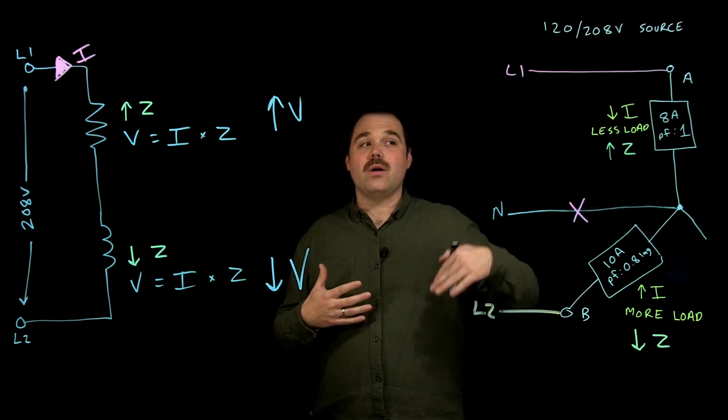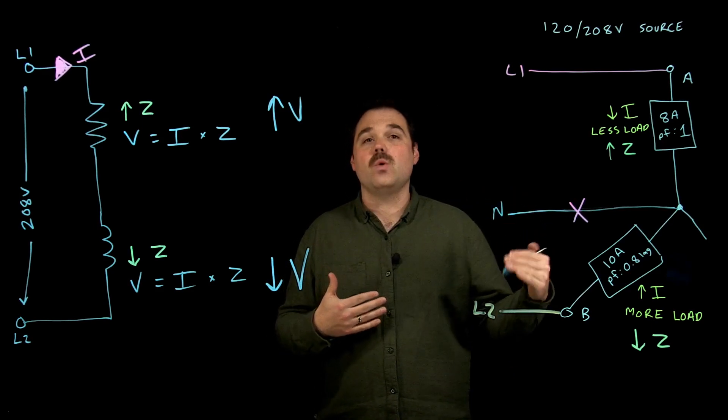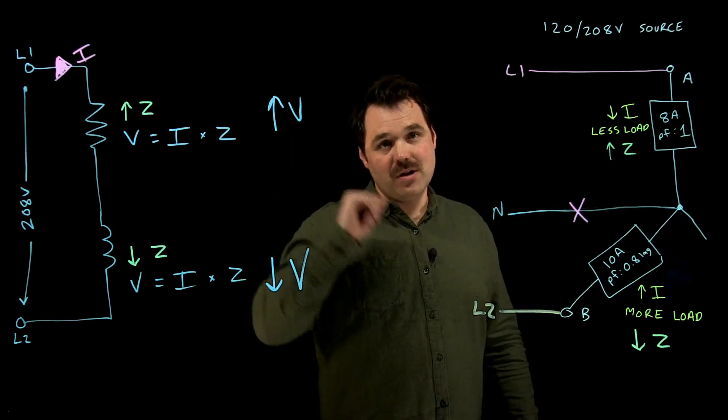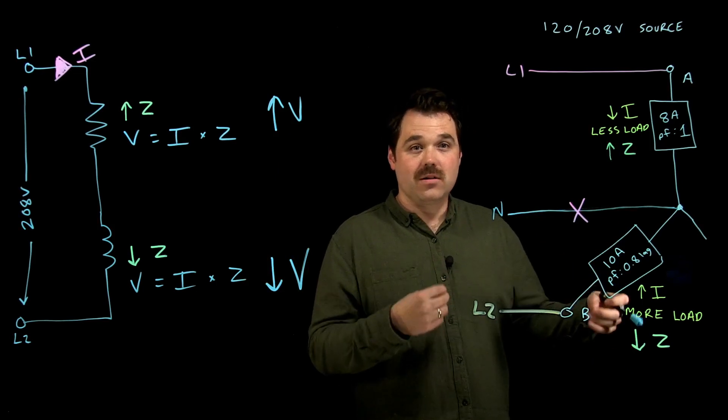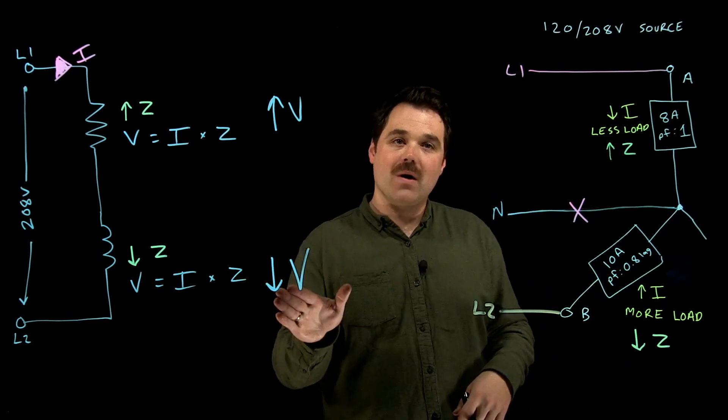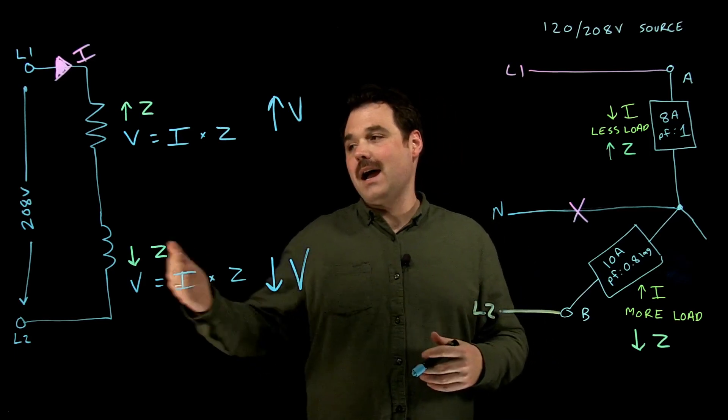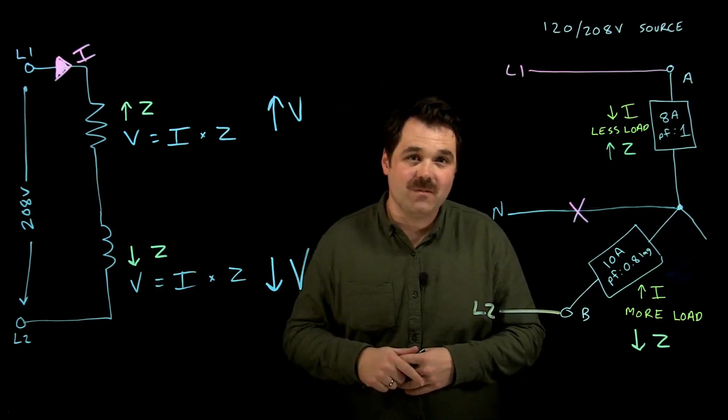So again, our least loaded circuit or the circuit with the highest impedance sees a higher volt drop. Our highest loaded circuit or our lowest impedance sees a lower voltage drop. And of course, those would vectorally add up to equal that 208 volts source.